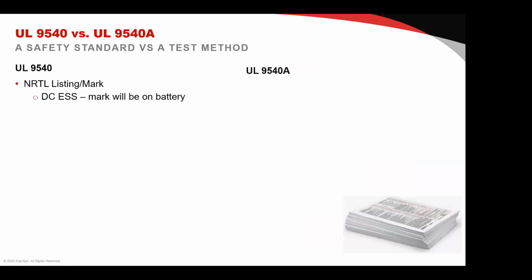So UL 9540, you can get that mark from a nationally recognized testing lab. That could be UL, could be CSA, the Canadian equivalent, could be Intertek. There are others, but it has to be a nationally recognized testing lab, and they can mark it as a DC ESS, so UL 9540 DC ESS. So that's the situation with battery manufacturers or people that only offer batteries.